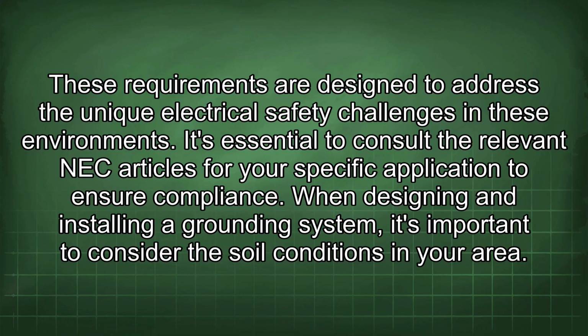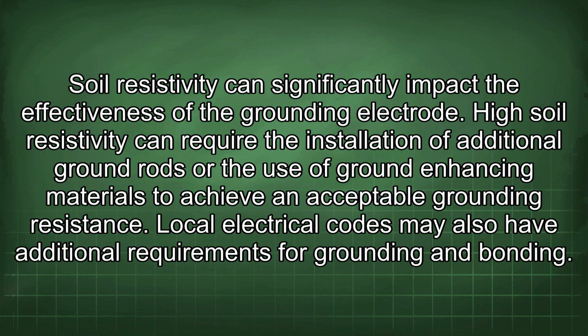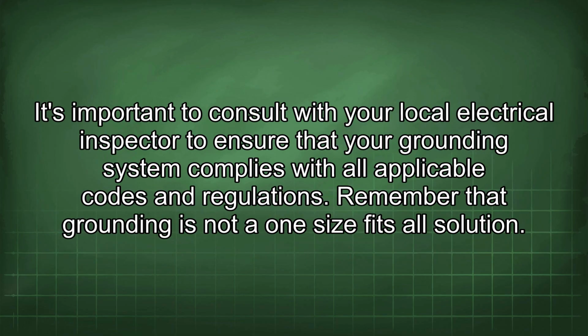When designing and installing a grounding system, it's important to consider the soil conditions in your area. Soil resistivity can significantly impact the effectiveness of the grounding electrode. High soil resistivity can require the installation of additional ground rods or the use of ground-enhancing materials to achieve an acceptable grounding resistance. Local electrical codes may also have additional requirements for grounding and bonding. It's important to consult with your local electrical inspector to ensure that your grounding system complies with all applicable codes and regulations.